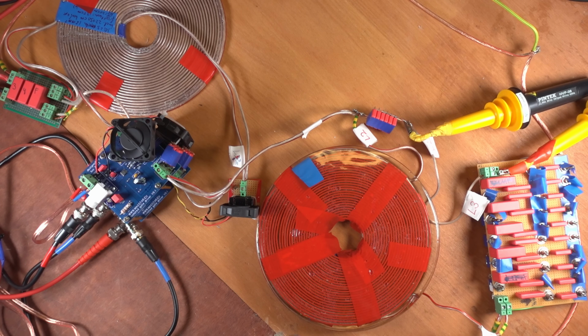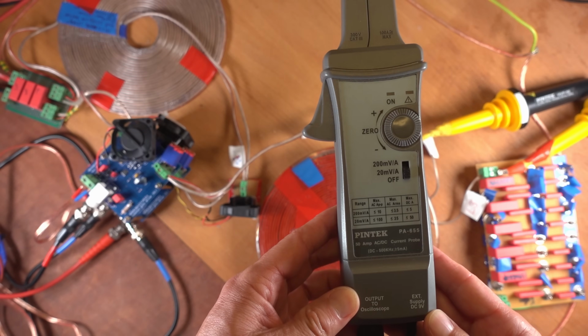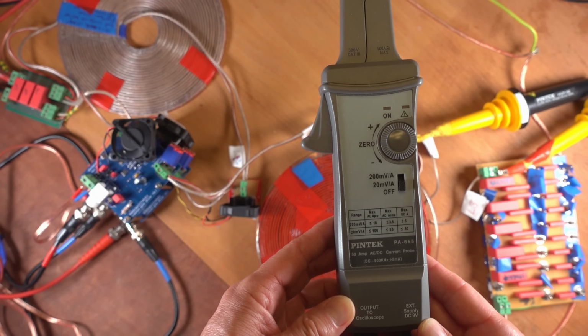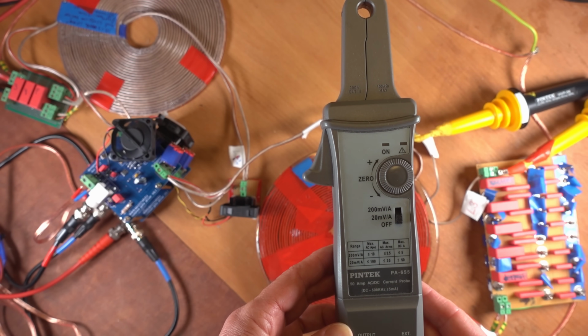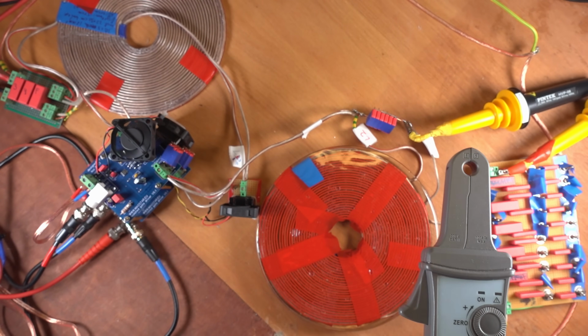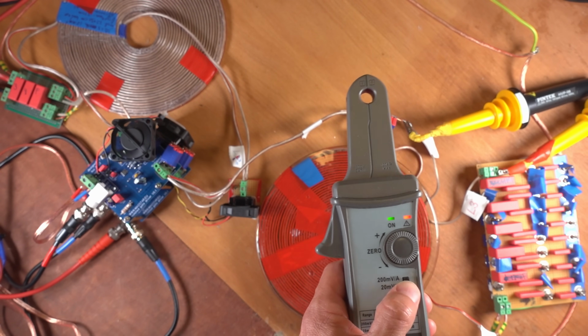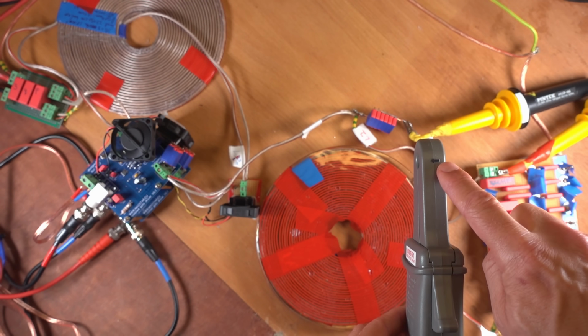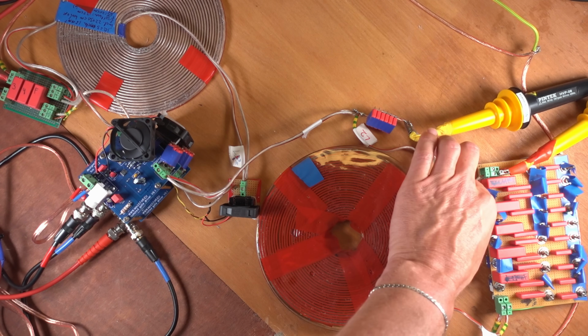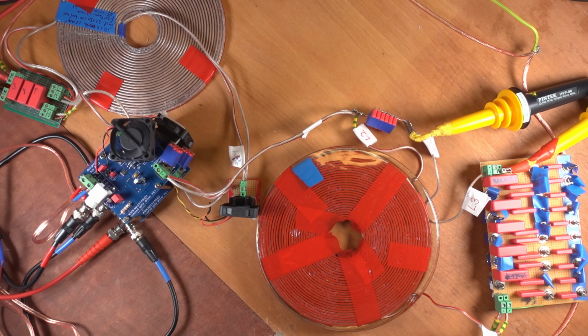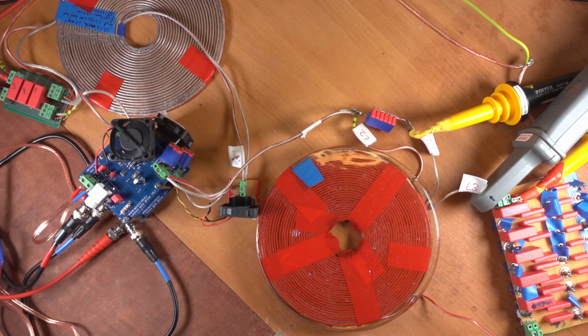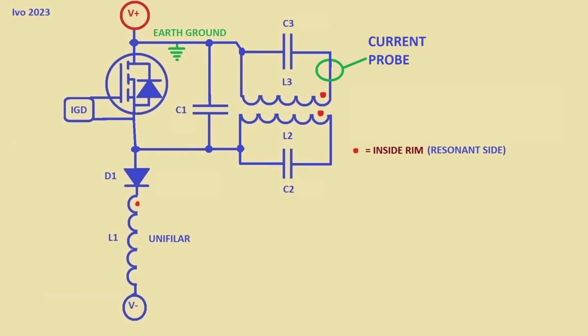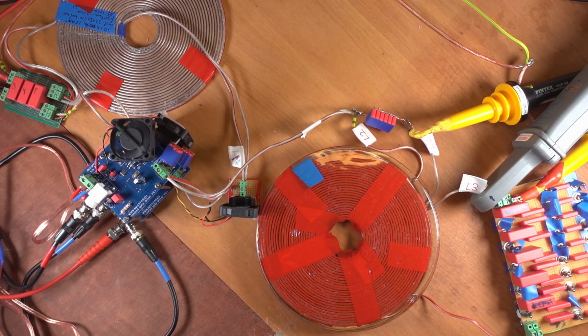Let me show you this with a current probe. So this is my current probe, it's a Pintek PA-655, rated for 500 kilocycles per second, and I'll put it on the 200 millivolt per amp setting. The arrow will point towards the coil, and I'll hook it up to the L3 inside rim, like so. Now the probe is set to AC measurement, so let's take a look at that current in the L3 coil. I'll turn the system on again.